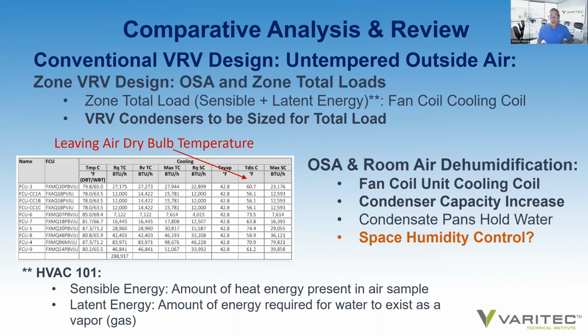Consequently, the indoor air handlers see full condensation of the latent component of the humidity at the indoor air handler. Consequently, condensate pans fill with water, and the VRV system is oversized in order to meet that peak summer design condition.